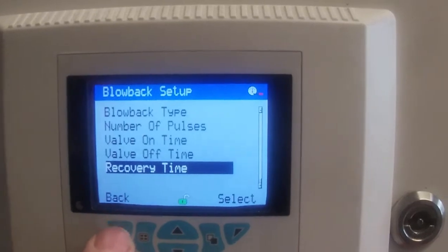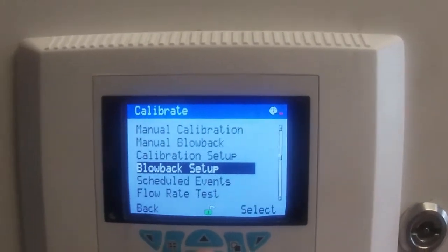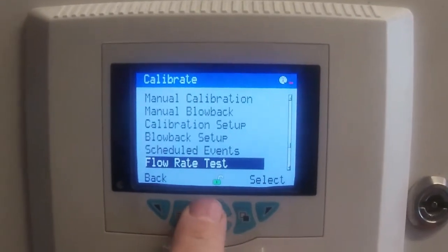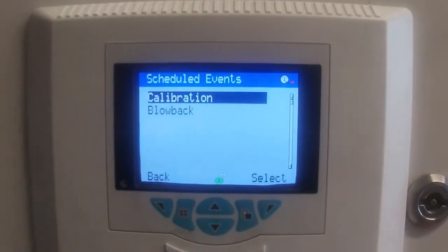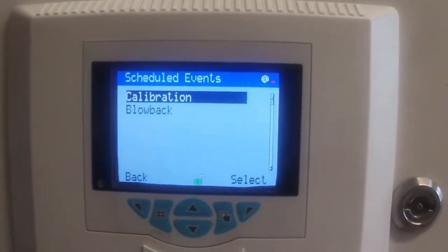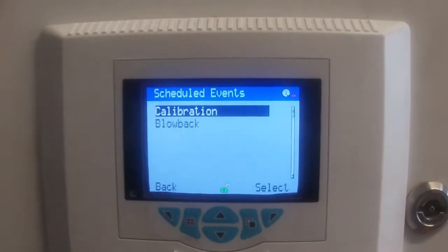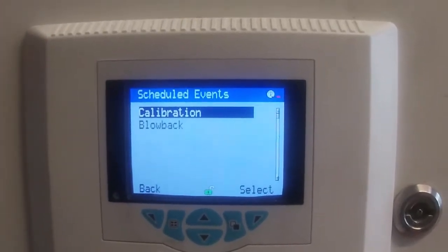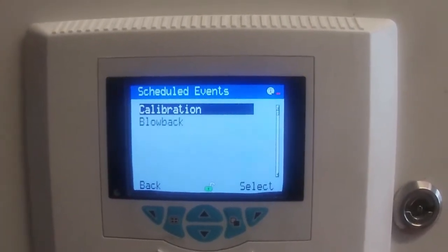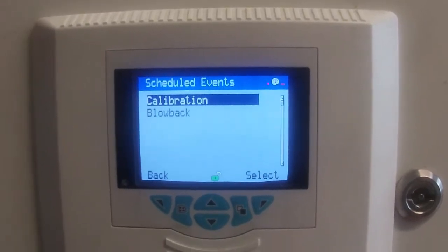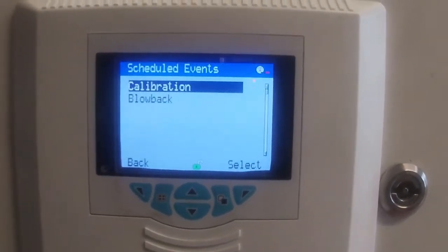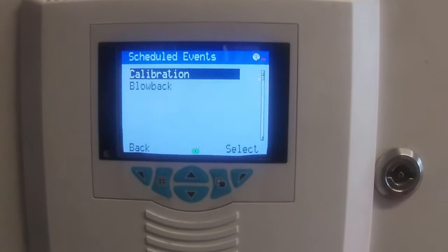Go back, scheduled events, you could actually schedule this thing to do calibrations and blowbacks at certain times. It can automatically do it. Personally, I don't like it because of the fact that you're going to be burning up a lot of gas. And I found that these do not really have problems with their calibration. They really are solid.